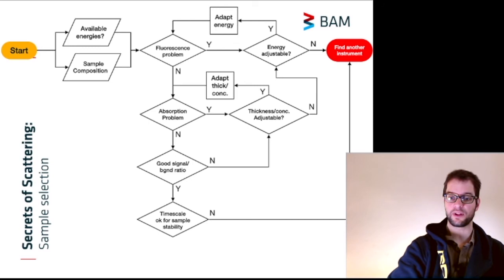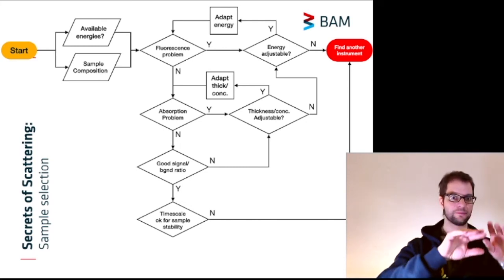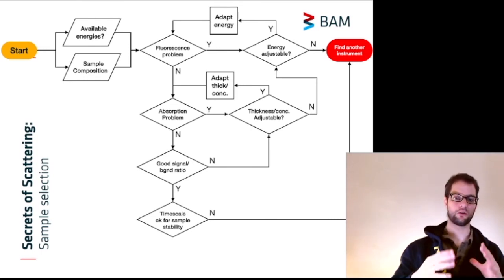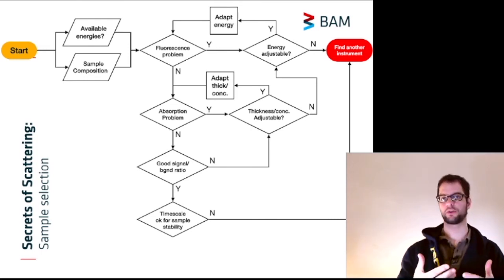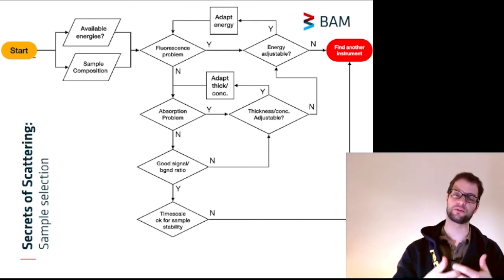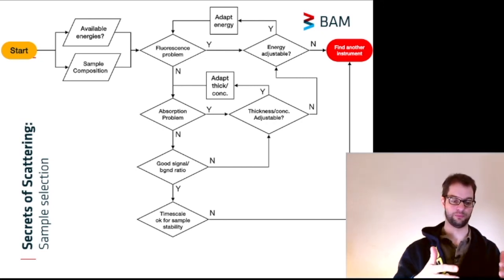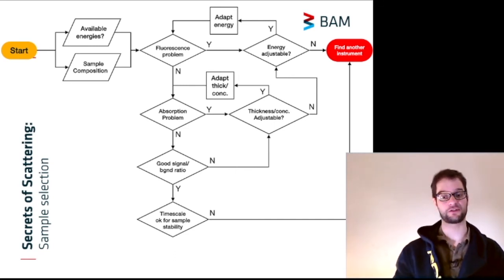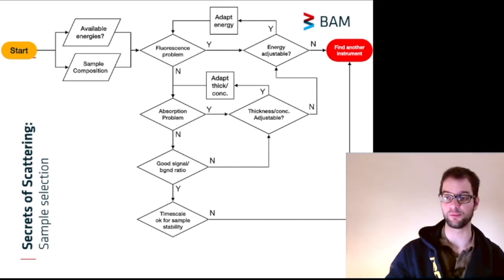Lastly, you want to check whether the time scale of the measurement is okay for your sample stability. In our laboratory instrument, we typically take about four to eight hours per sample. If you have a sample which sediments, for example, or which deteriorates over that amount of time, or if you want to measure scattering from sample developments over time that happen on a short timescale, for example, you're looking at a particle growth in a reaction, then the laboratory instrument is not the correct instrument for you. You will want to go to a beamline in that case.